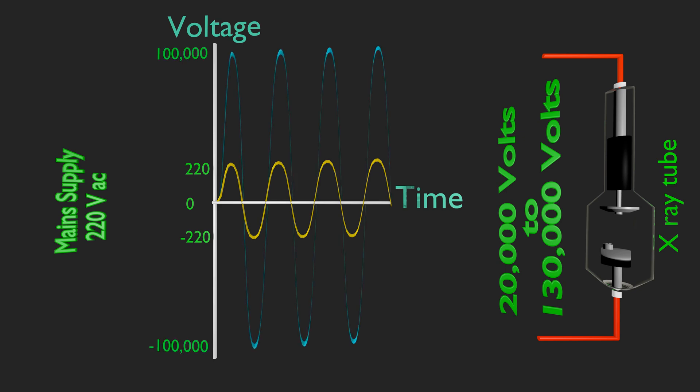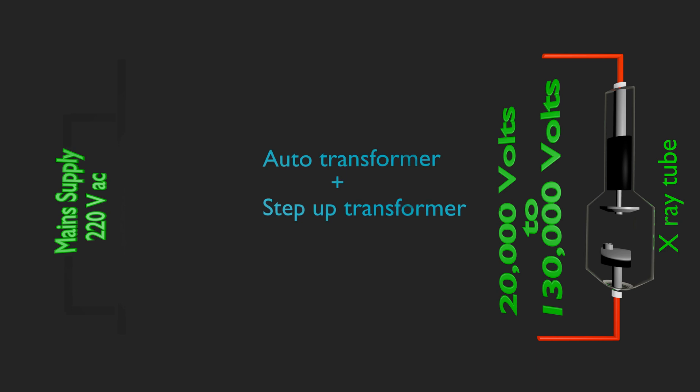We need to increase this 220 voltage AC supply to kilovoltage range. This change is usually achieved by combination of two transformers. Firstly, by using an auto transformer, and secondly by a step-up transformer.